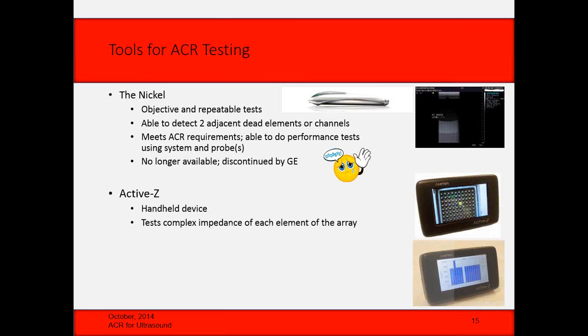The Active-Z is a little handheld device that today can test the complex impedance of every element of the array. So as you see in that picture, it's like a smartphone. It's the size of an iPhone or something. And you turn it on and you tell it, I want to test a Siemens probe. And then it asks you to select a section of the probe you want to test first. So they divide the probe up into 9 sets of elements, typically. I think it's 9.